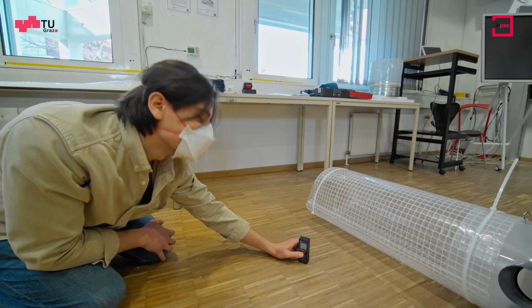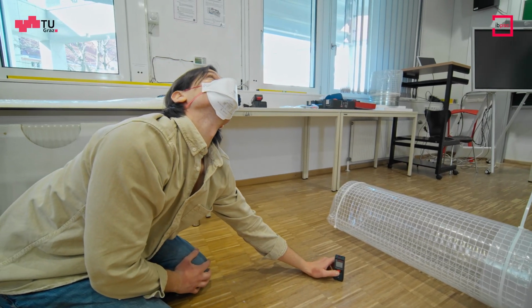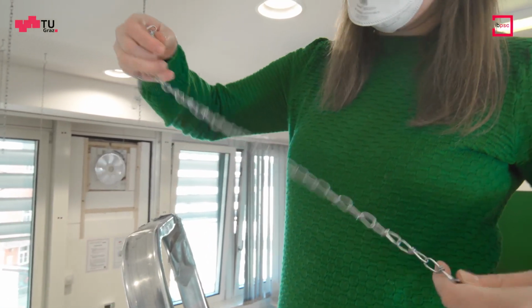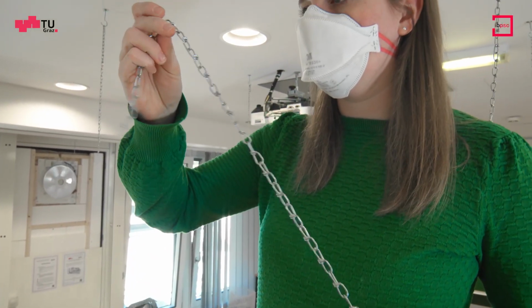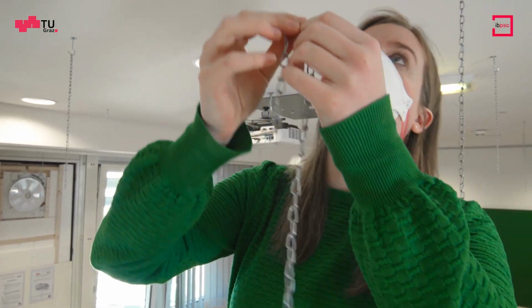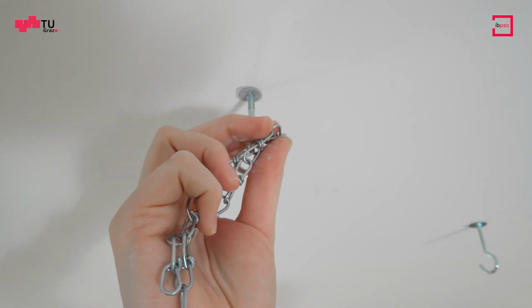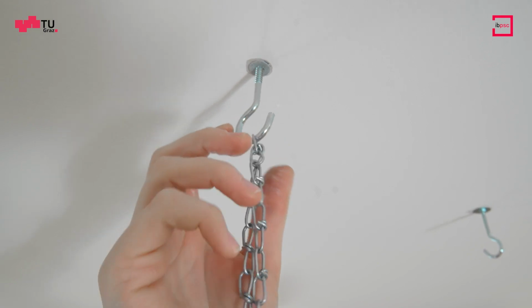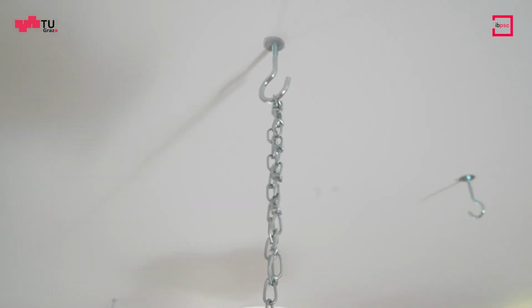It's helpful to use a portable laser to make sure the line is straight, but you could also use a piece of string and a spirit level. We recommend using lightweight galvanized steel chain to suspend the ductwork. This is easy to work with and also fire resistant, which means the system will remain suspended in the event of a fire evacuation. The chain also makes it easy to fine-tune the ductwork so that it is uniformly level.